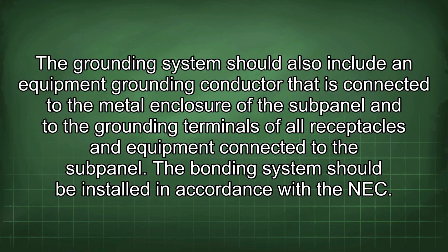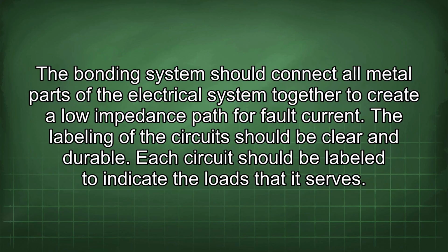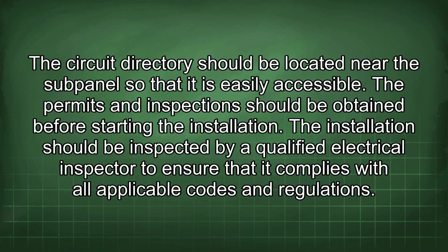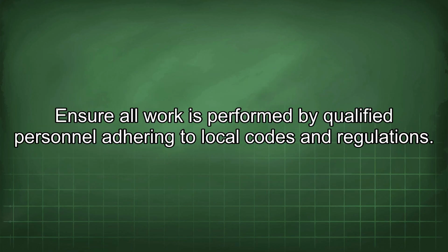The bonding system should be installed in accordance with the NEC. The bonding system should connect all metal parts of the electrical system together to create a low impedance path for fault current. The labeling of the circuit should be clear and durable. Each circuit should be labeled to indicate the loads that it serves. The circuit directory should be located near the subpanel so that it is easily accessible. The permits and inspections should be obtained before starting the installation. The installation should be inspected by a qualified electrical inspector to ensure that it complies with all applicable codes and regulations. Ensure all work is performed by qualified personnel adhering to local codes and regulations.